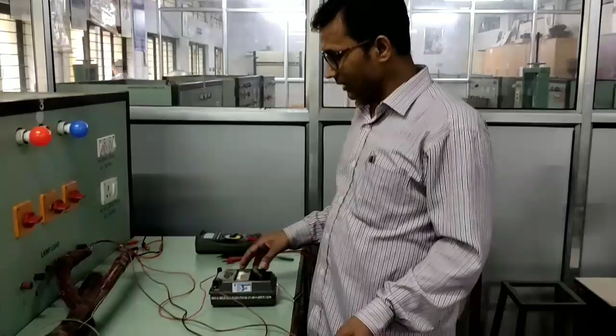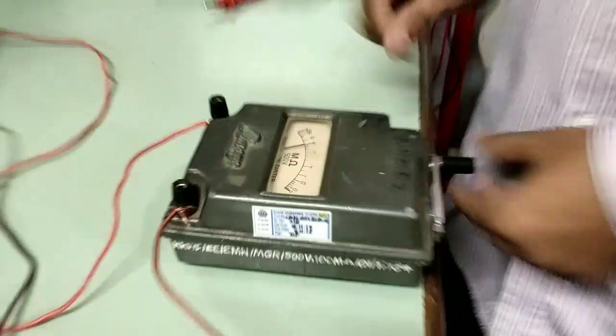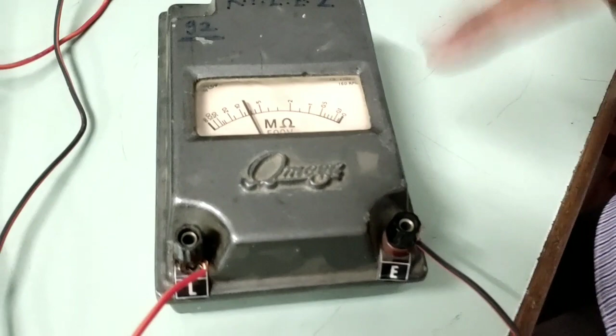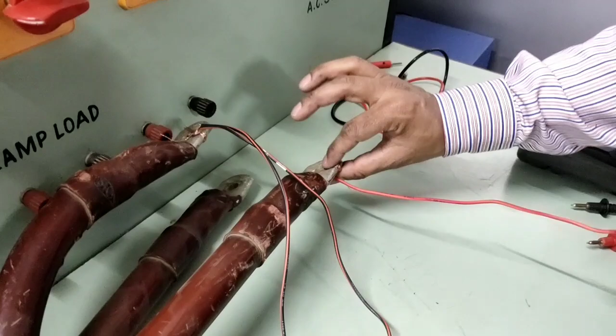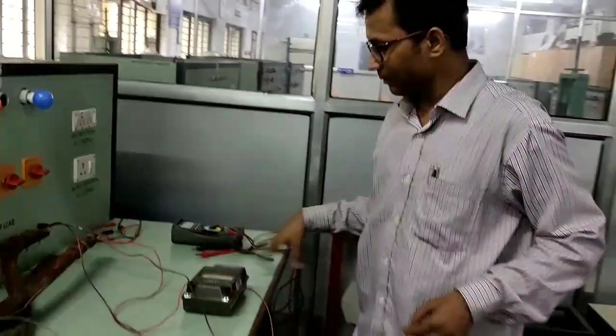Students, this is the actual practical setup of the Megger used to measure insulation resistance of the cable. This is a Megger. You can see its scale, 500 volt, megaohm. Then L terminal, E terminal. Here is its handle. Okay. The L wire is connected to one conductor of the cable. Another E wire is connected to another conductor of the cable, and this is connected to the sheath and from there to earth. It is for protection purpose.